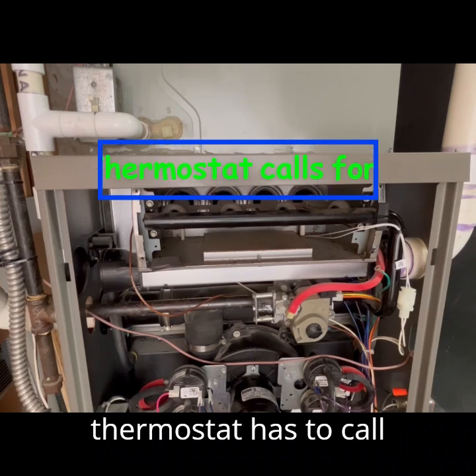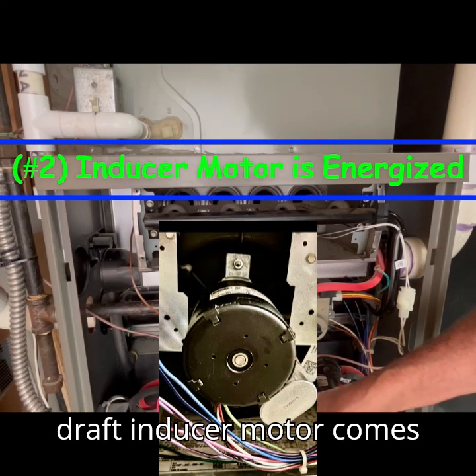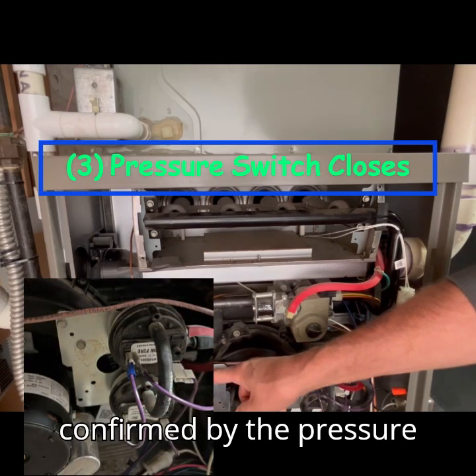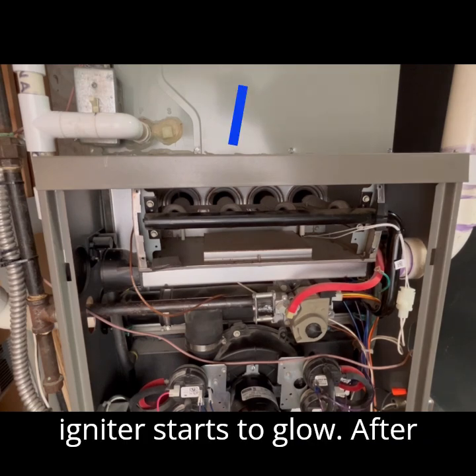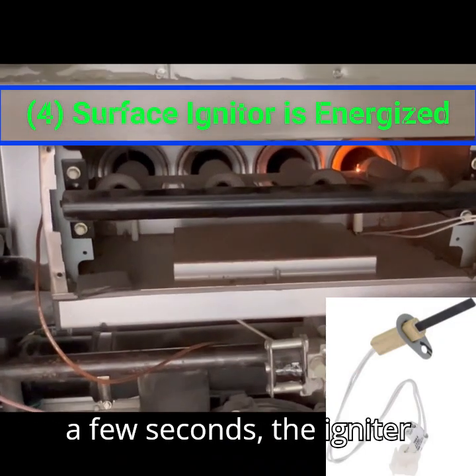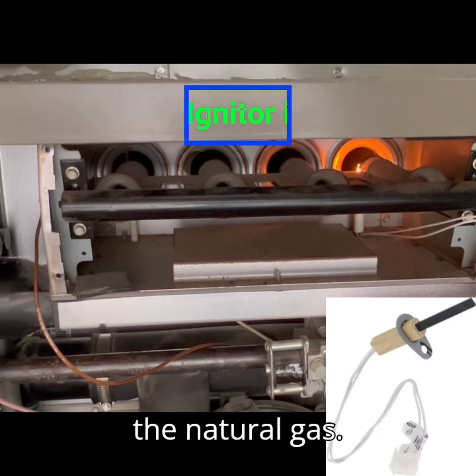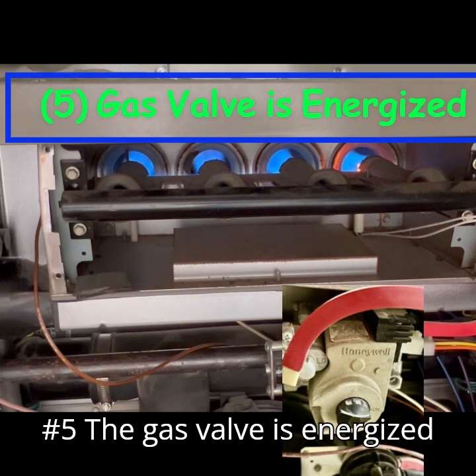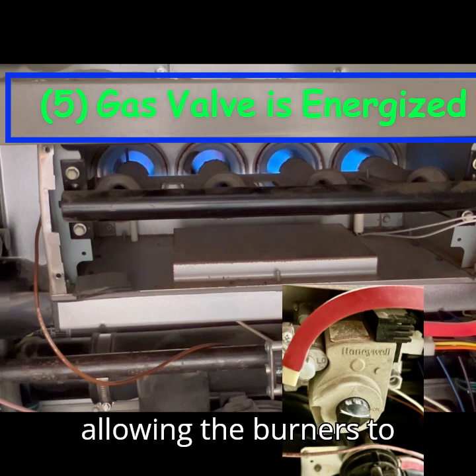Number one, the thermostat has to call for heat. Number two, your draft inducer motor comes on. Number three, the draft motor operation is confirmed by the pressure switch. Number four, the surface igniter starts to glow. After a few seconds, the igniter will get hot enough to ignite the natural gas. Number five, the gas valve is energized and opens to allow gas to flow through the burner, thus allowing the burners to ignite.